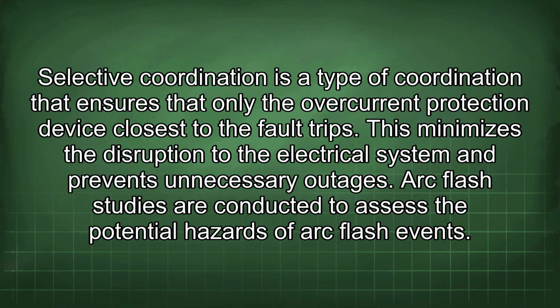Selective coordination is a type of coordination that ensures that only the overcurrent protection device closest to the fault trips. This minimizes the disruption to the electrical system and prevents unnecessary outages.